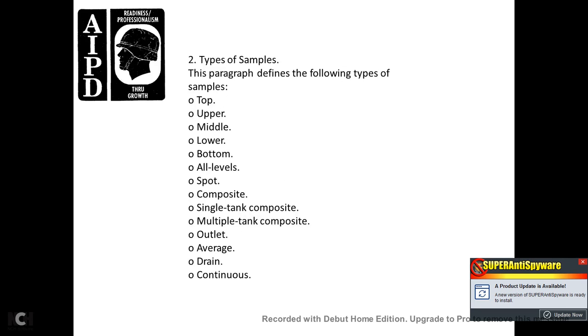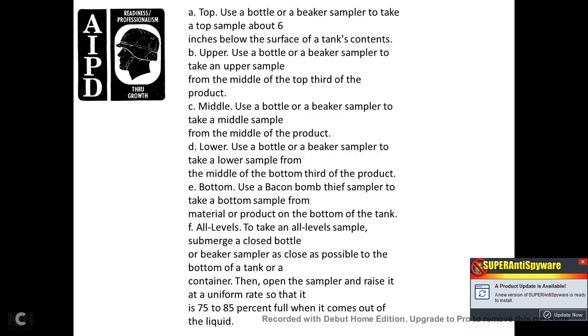Types of samples. The following types of samples are defined: top, upper, middle, lower, bottom, all levels, composite, single tank composite, multiple tank composite, outlet, average, and drain. Top sample: uses a bottle or beaker to take a sample six inches below the surface of the tank contents. Upper sample: a bottle or beaker sample taken from the upper one-third of the product. Middle sample: taken from the middle of the product. Lower sample: taken from the lower one-third of the product. Bottom sample: uses a Bacon bomb thief sampler to take a sample of material at the bottom of the tank.